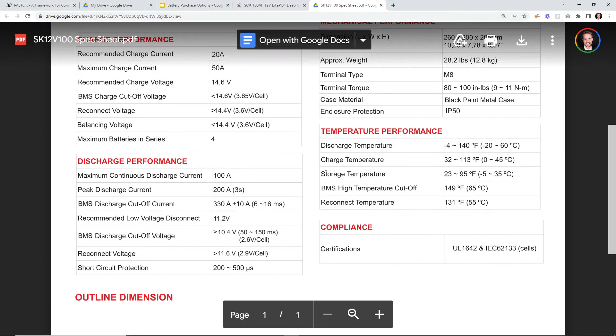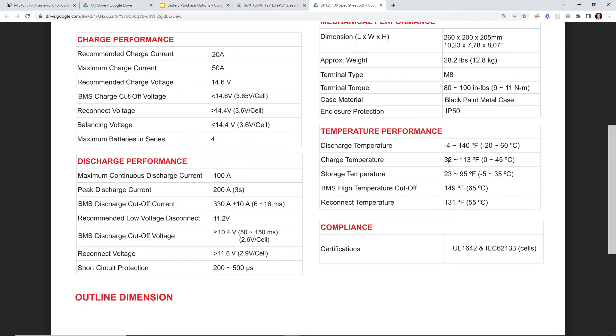All right, here's the next important part. So discharge temperatures: it'll discharge down to -4 and up to 140 degrees Fahrenheit. It'll charge in a range of 32 degrees to 113 degrees. This is storage. BMS high temp cutoff is at 149 degrees. The reconnect is at 131. But Will Prowse did test it, and this 32 right here, that is the low temperature disconnect, so that's why it does not operate below that.